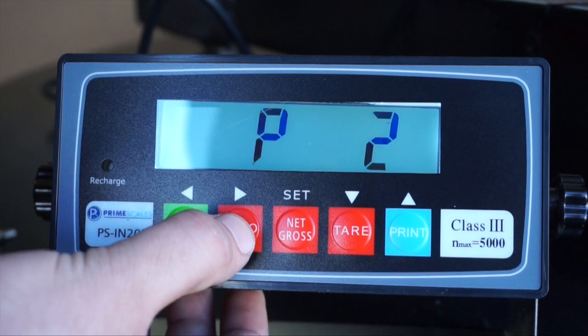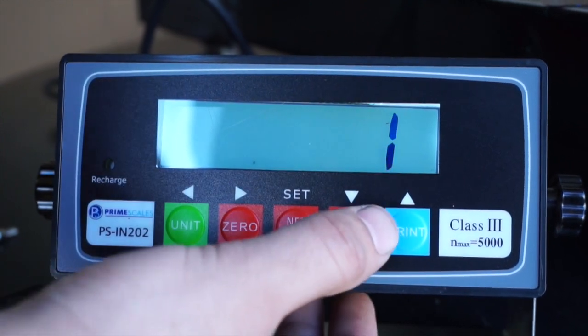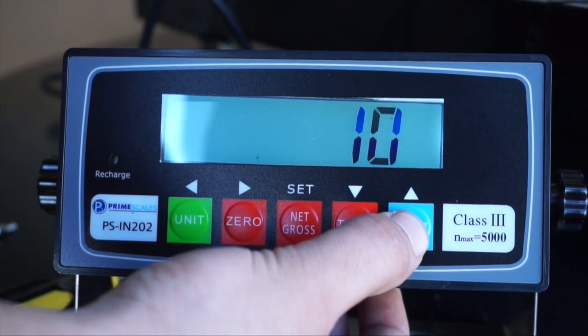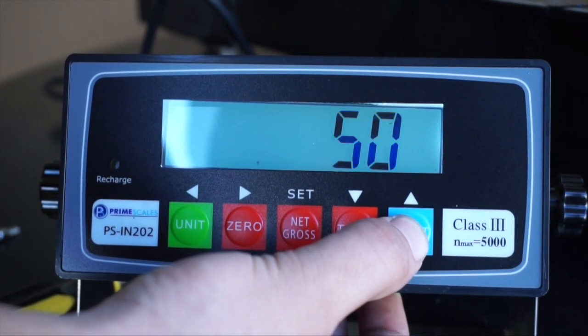Press print to move to P2. Parameter 2 or P2 sets the accuracy of the scale. Enter P2 by pressing the zero button.